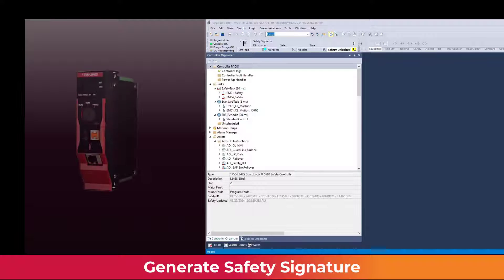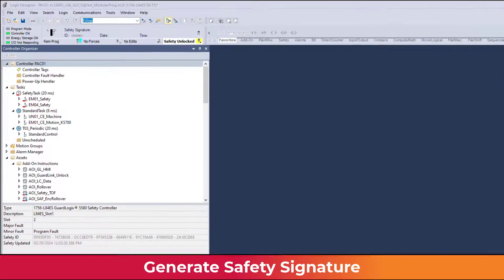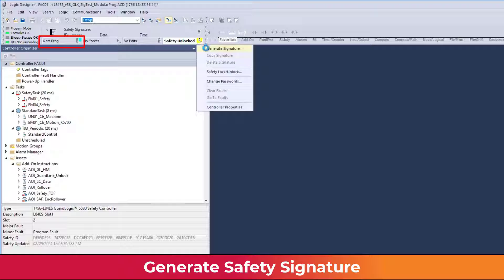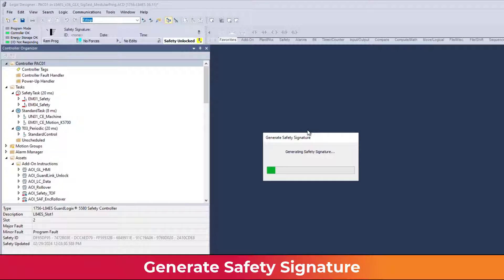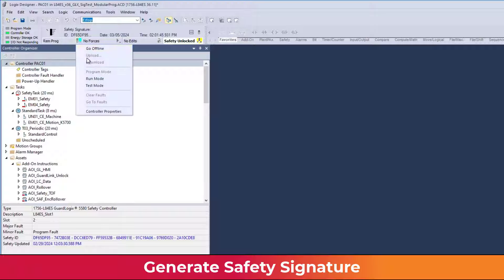A GuardLogix application must be downloaded to a physical controller to create a controller safety signature. While the controller is in program mode, select Generate Signature from either the Controller Properties Safety tab or from the Controller Status Safety pull-down menu. The signature generation process creates new signatures where none exist, and either updates or validates any existing signature elements.